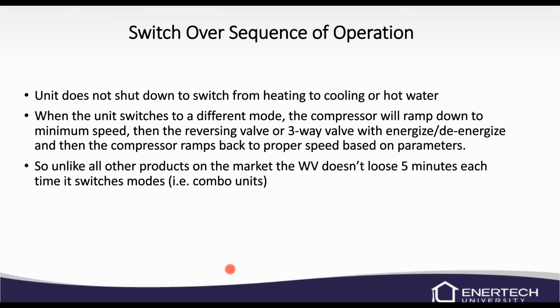When we're switching from heating to cooling or hot water, the unit does not shut down. Basically, the compressor is going to ramp down to minimum speed. If you're going into cooling, your reversing valve will be energized. If you're going into hot water, the 3-way valve will be energized. And then the compressor is going to ramp back up to proper speed based on your parameters. So unlike our combo unit or any of our other units, we don't lose that 5-minute time when we're switching modes. Makes it kind of nice. We can almost switch on the fly.